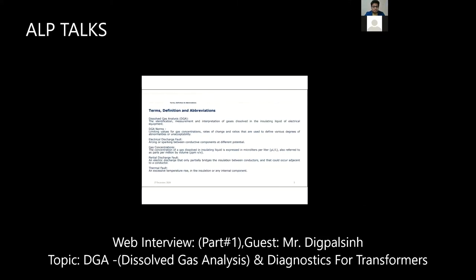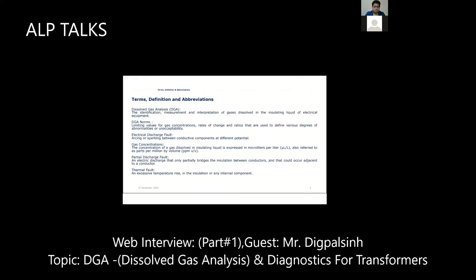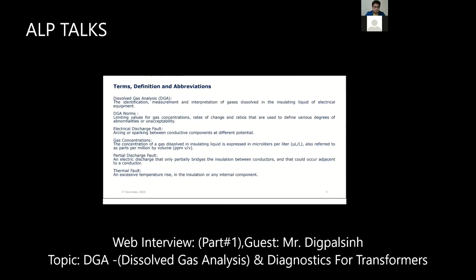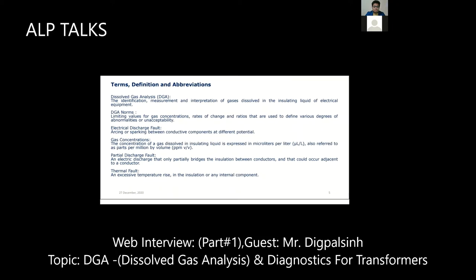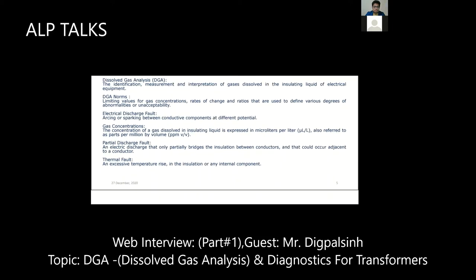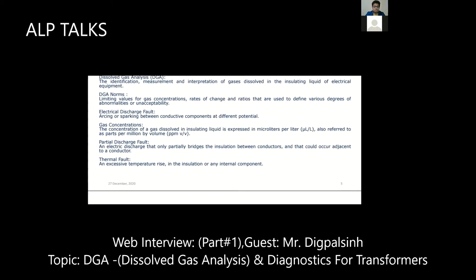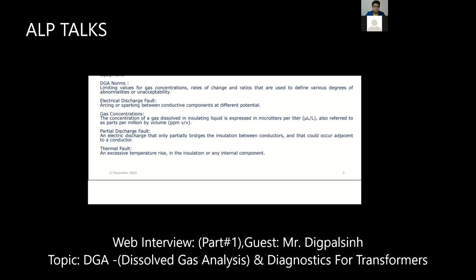Then some terms and definitions. The main term is dissolved gas analysis, which we have already discussed. It is the identification, measurement, and interpretation of gases dissolved or formed inside mineral oil in any electrical equipment, let's say a transformer or any switchgear. Then DGA norms. Electrical discharge fault: everyone knows, any arcing or sparking creates discharge in mineral oil or paper. That is electrical discharge.